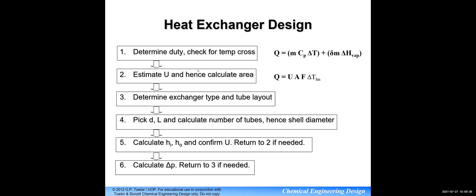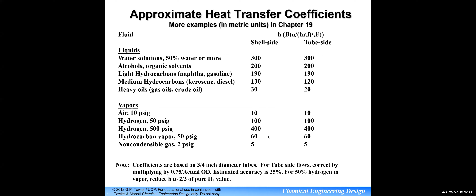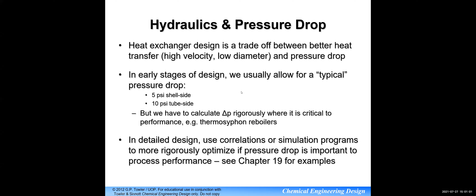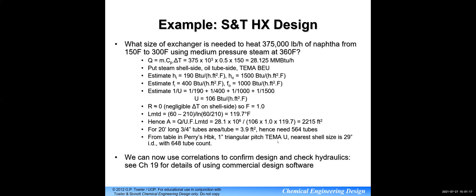From the heat exchanger designs, there are some calculations you may want to run. What we want to see here is some approximations for the heat transfer coefficients. You can find this in the chemical engineering design book by Towler, which covers estimation of heat transfer coefficients, fouling factors, and pressure drop from heat exchangers. This calculation helps you figure out how much surface area you need, how many tubes you want, and what kind of heat exchanger type you may need for the problem.